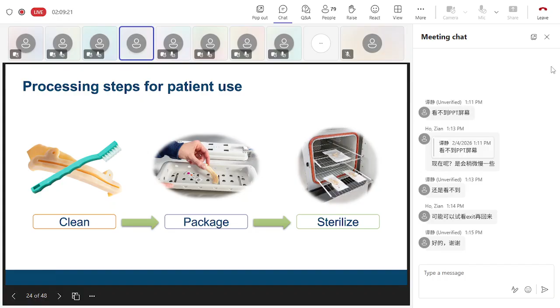So cleaning is performed in the CSSD to remove contaminants and reduce microbial contamination that the 3D printed medical device may have been exposed to during the actual process of manufacturing. After the device is cleaned, rinsed and dried, it must be packaged for sterilisation, just like all other products or devices in the CSSD. The device, along with a chemical indicator, is placed within a barrier system in preparation for sterilisation. Typical barrier systems used in CSSD include sterilisation wrap, sterilisation pouches and container systems. And the last step is sterilisation. And the most common sterilisation applications within healthcare facilities include steam sterilisation and vapour hydrogen peroxide sterilisation.